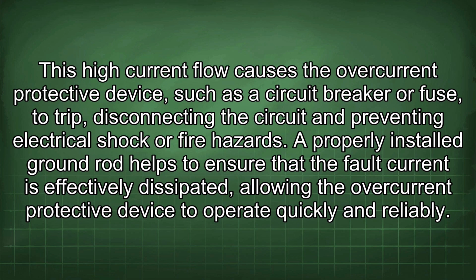This high current flow causes the overcurrent protective device, such as a circuit breaker or fuse, to trip, disconnecting the circuit and preventing electrical shock or fire hazards. A properly installed ground rod helps to ensure that the fault current is effectively dissipated, allowing the overcurrent protective device to operate quickly and reliably.